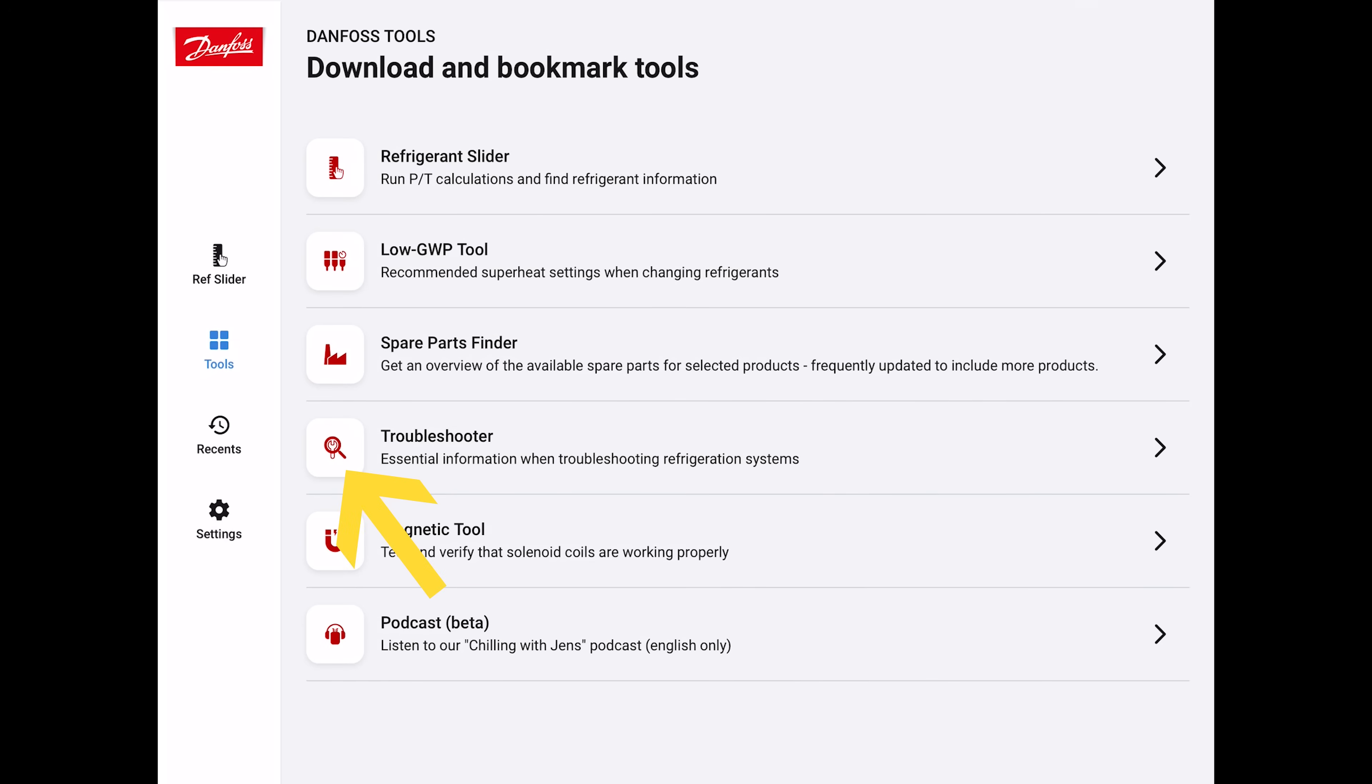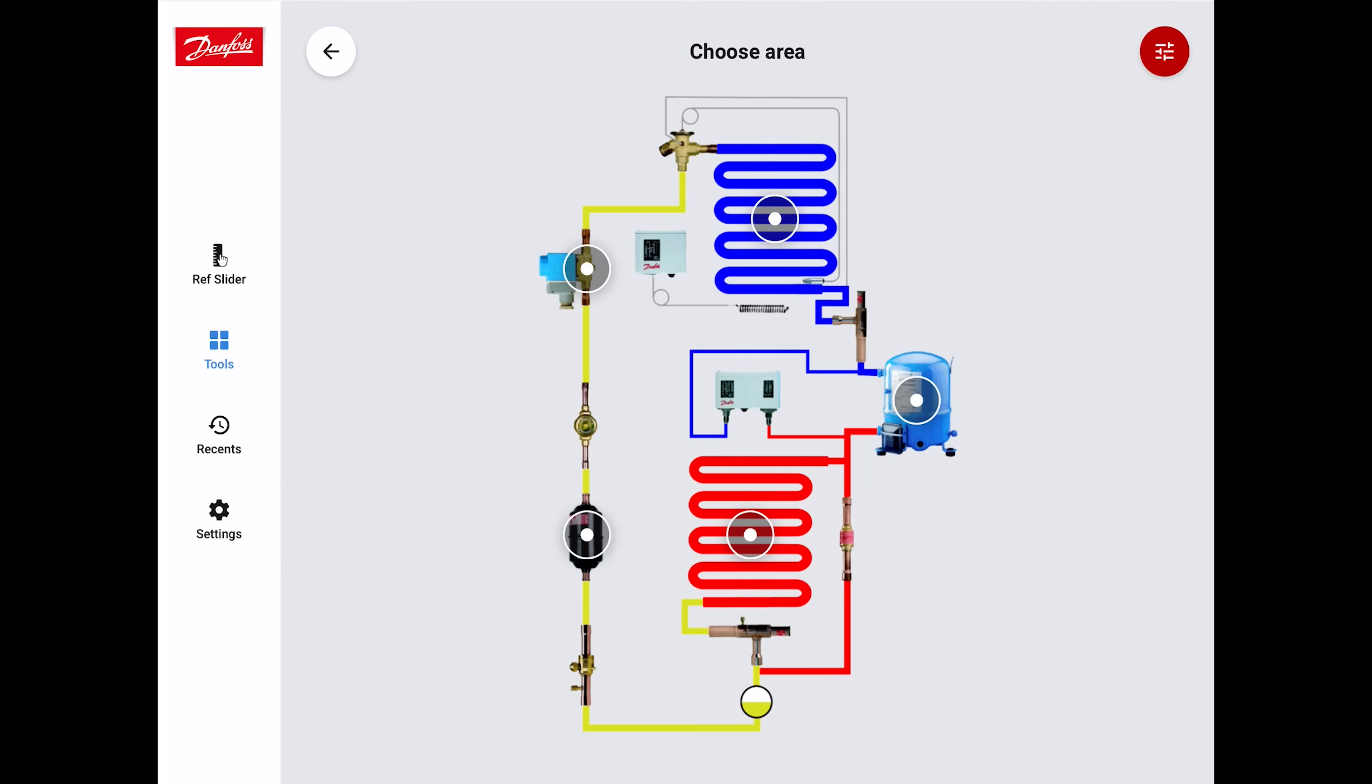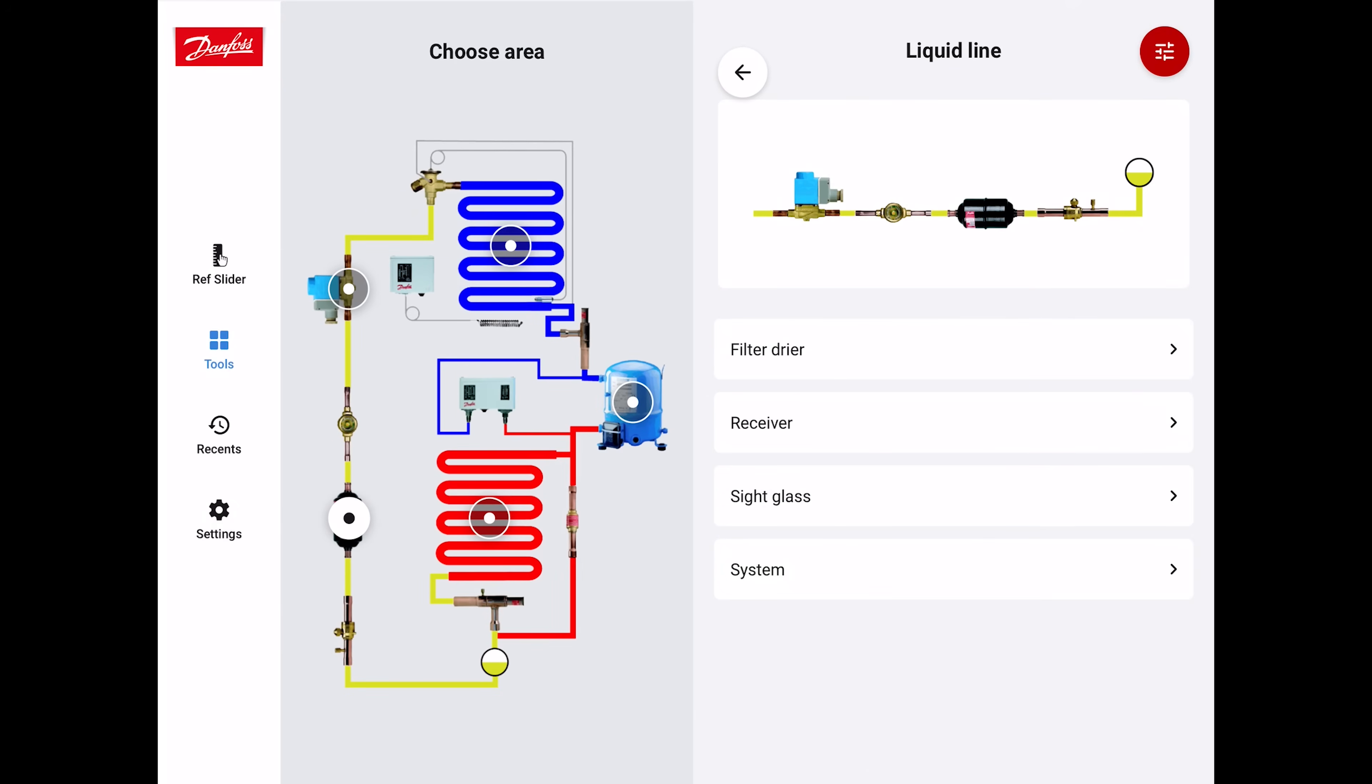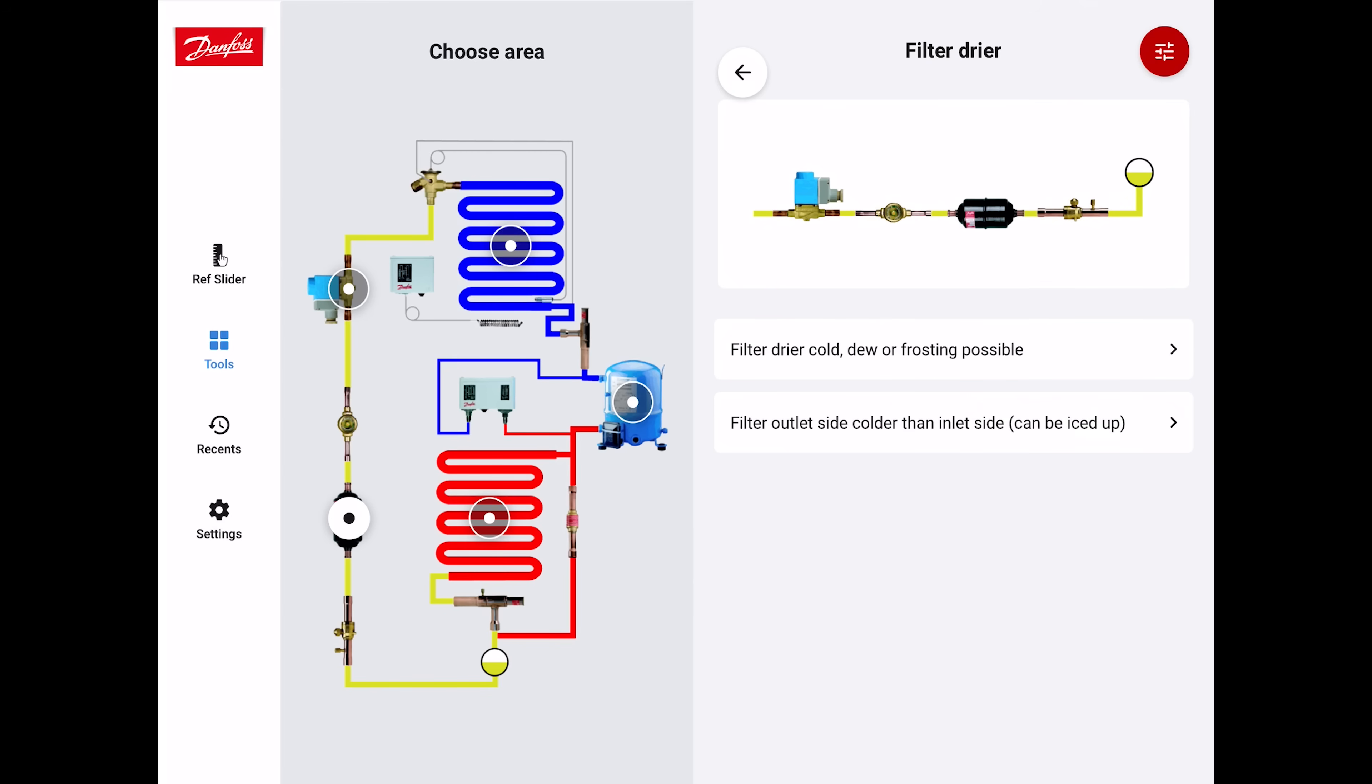Now let's go to the troubleshooter. You can click on any part of this and then enter into what the possible problem could be. Let's click on the filter dryer. It's giving you several items right around the filter dryer, but we're going to go to just the filter dryer by itself. It says filter outlet side colder than the inlet side can be iced up.